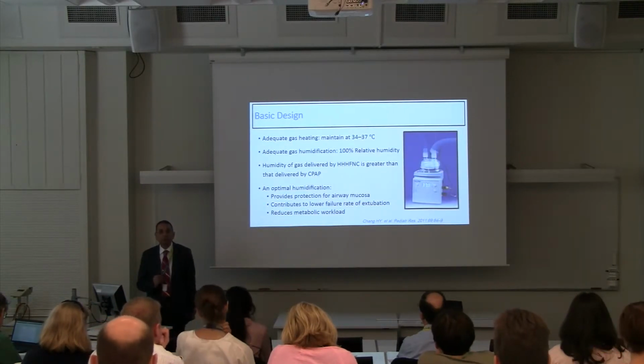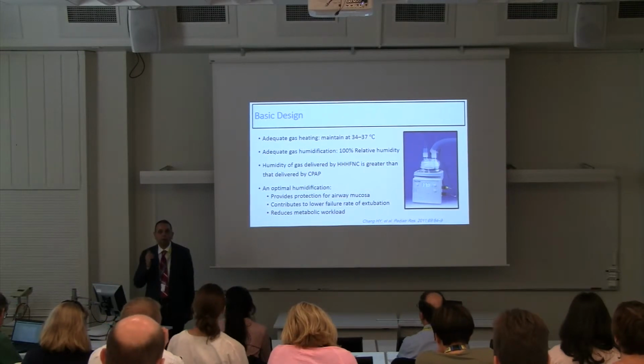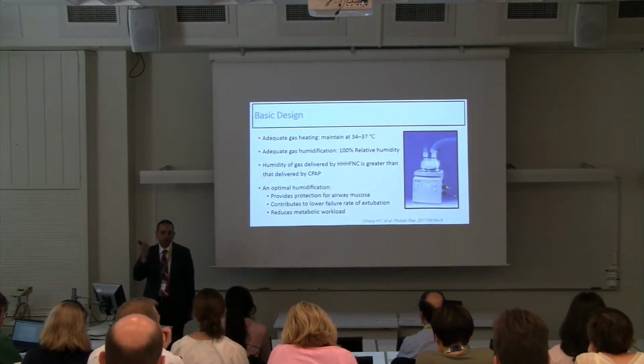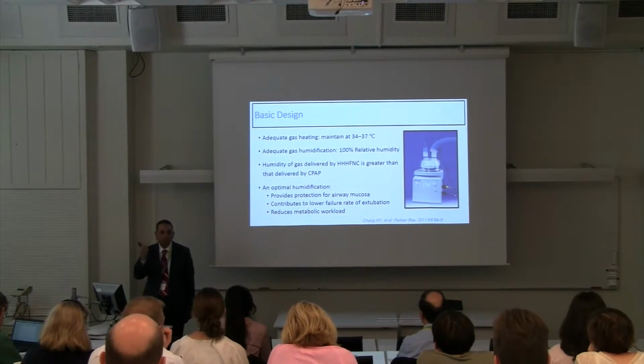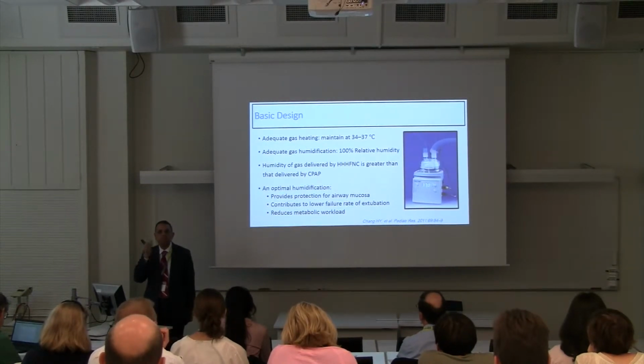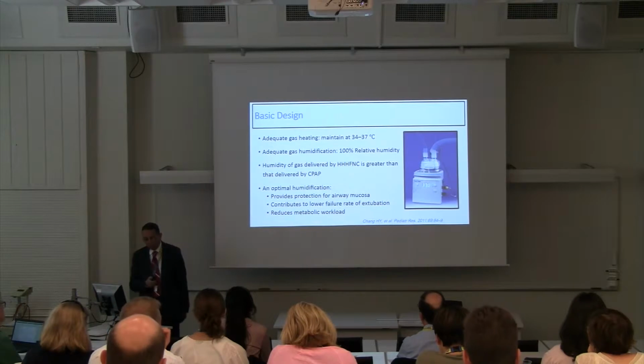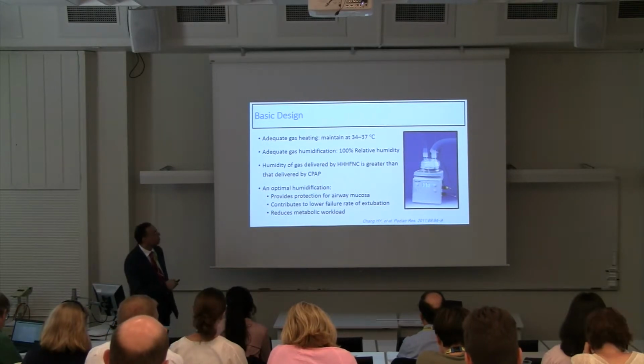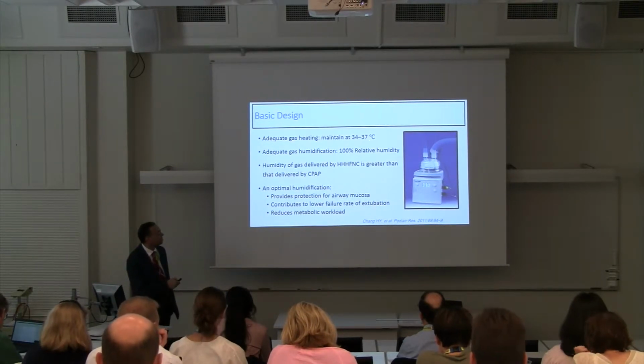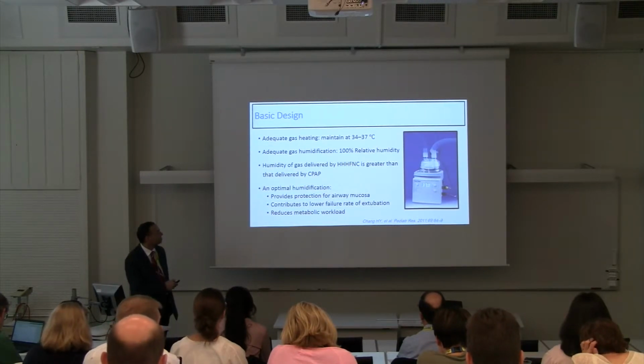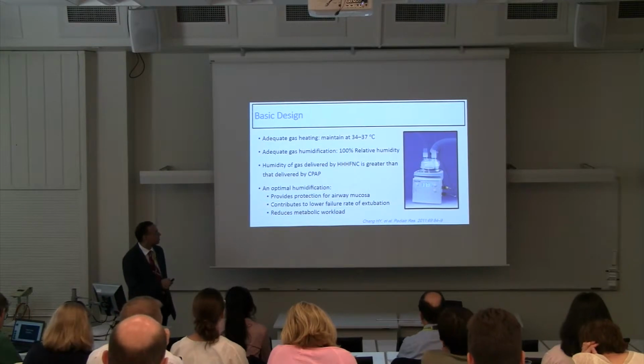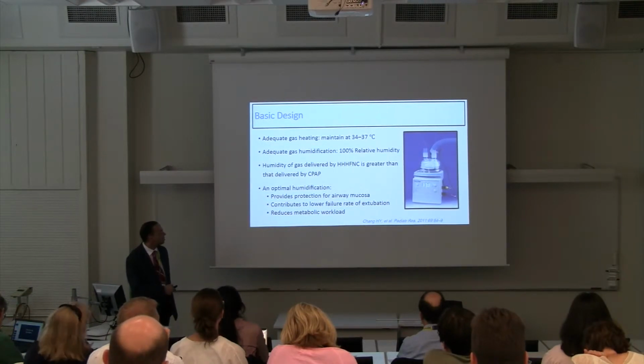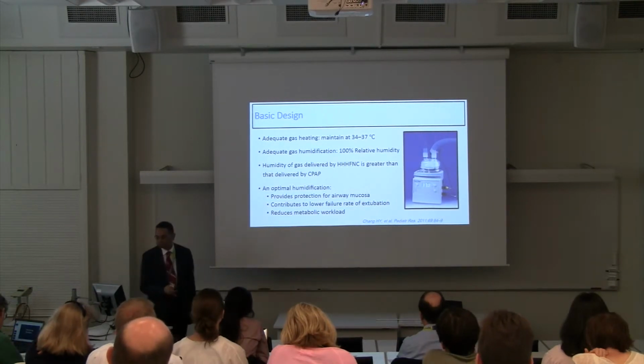So remember that the triple H you are talking about is heated, humidified, high flow nasal cannula. So the flow should be more than 2. There should be adequate heating and adequate humidification. The temperature of the inspired gas should be between 34 and 37 degrees centigrade, and 100% relative humidity is important. Humidification is important because it provides protection to the airway mucosa, contributes to a lower failure rate of extubation, and reduces metabolic workload.